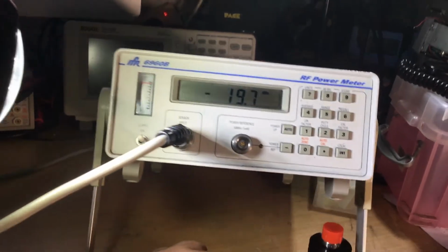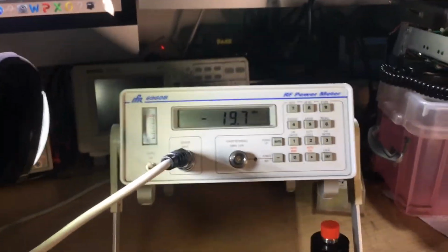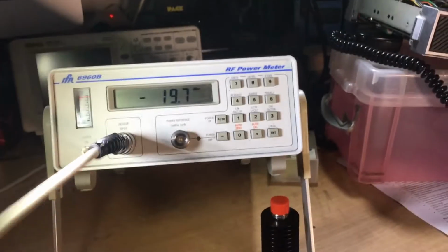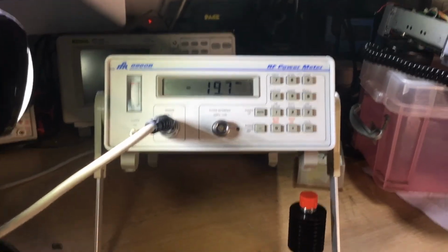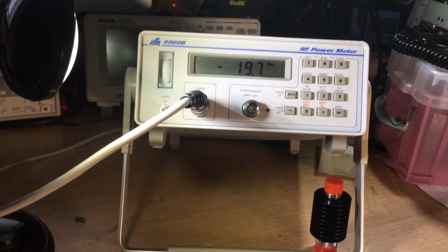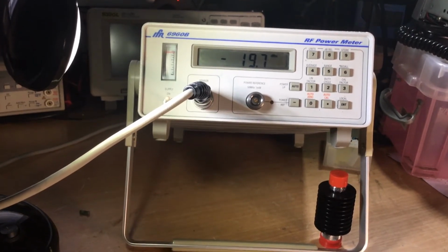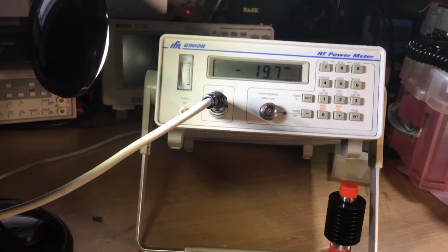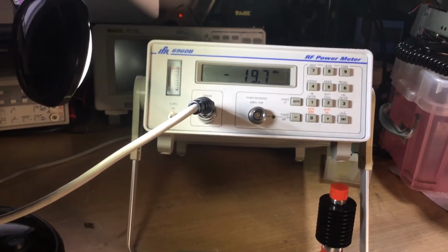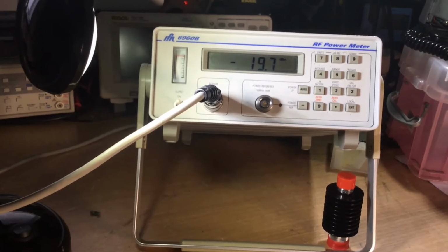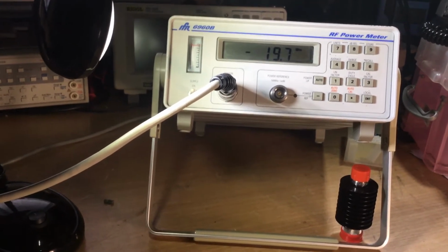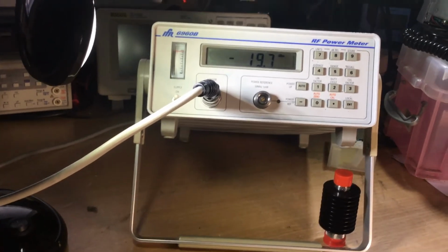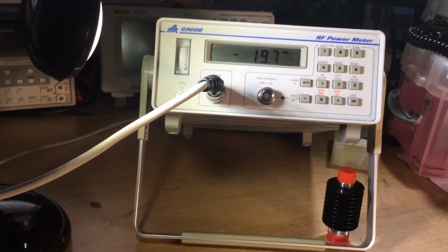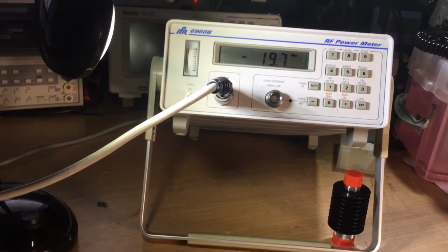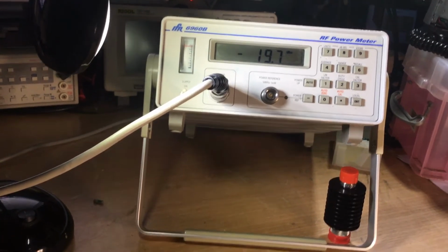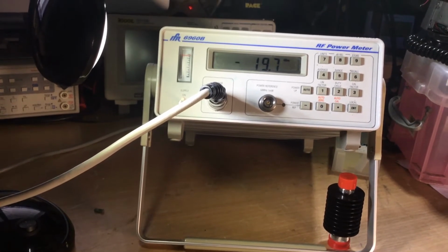So yeah, the technical blurb on these, written by Aeroflex, which I'm going to discuss now. It says that it's a precision power meter with comprehensive GPIB facilities for ATE, automated test equipment requirements and standard bench applications. Anyway, it says it's got an extensive frequency range of 30 kHz to 46 GHz. It's got a wide dynamic range, depending on what sensor you use with it, from -70 dBm, which is equivalent to 100 picowatts, to plus 44 dBm, which is 25 watts.